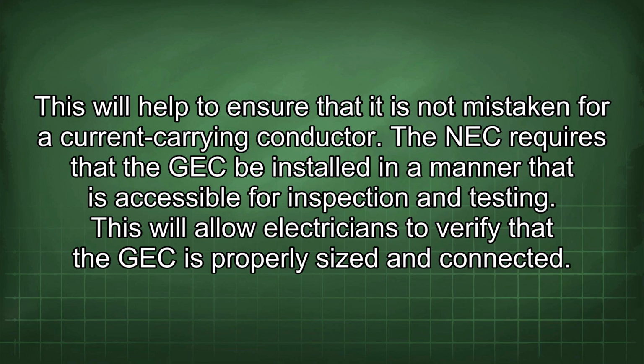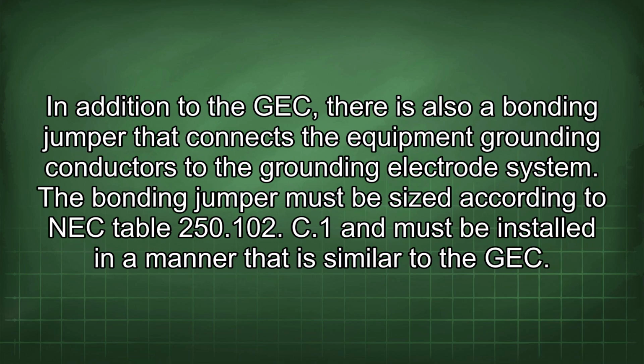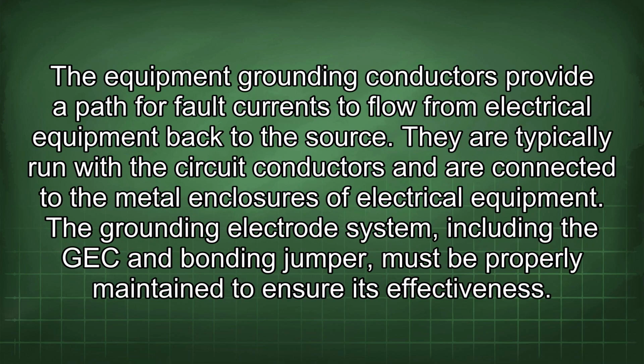The NEC requires that the GEC be installed in a manner that is accessible for inspection and testing. This will allow electricians to verify that the GEC is properly sized and connected. In addition to the GEC, there is also a bonding jumper that connects the equipment grounding conductors to the grounding electrode system. The bonding jumper must be sized according to NEC Table 250.102(C)(1) and must be installed in a manner that is similar to the GEC. The equipment grounding conductors provide a path for fault currents to flow from electrical equipment back to the source. They are typically run with the circuit conductors and are connected to the metal enclosures of electrical equipment.